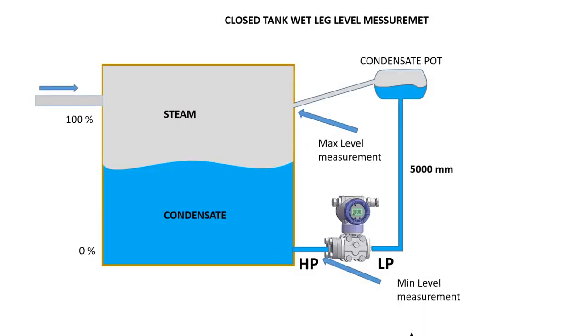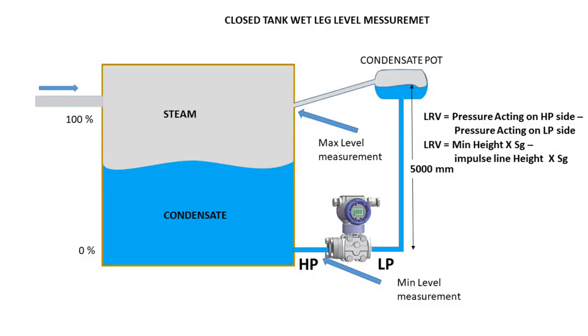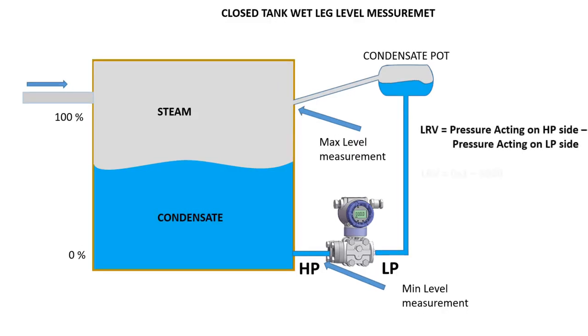First we calculate LRV. We take the height of the impulse line connected to the LP side of the transmitter as 5000 mm. The HP side pressure equals minimum measuring height times specific gravity of the condensate liquid. The LP side pressure equals height of the impulse line times specific gravity of the filled liquid. So the LRV equals 0 times 1 minus 5000 times 1.